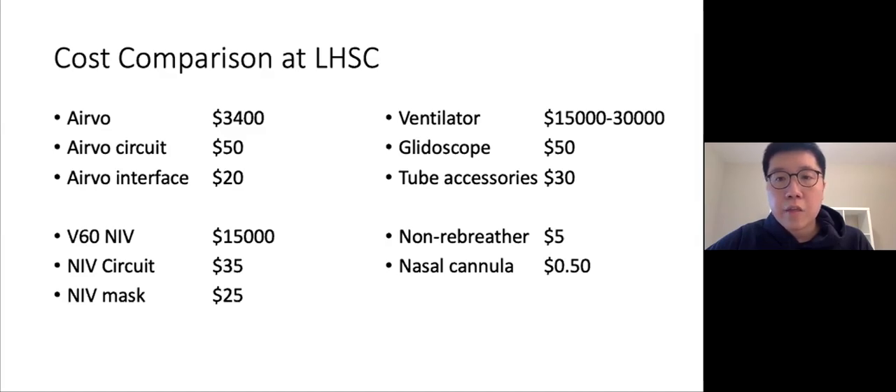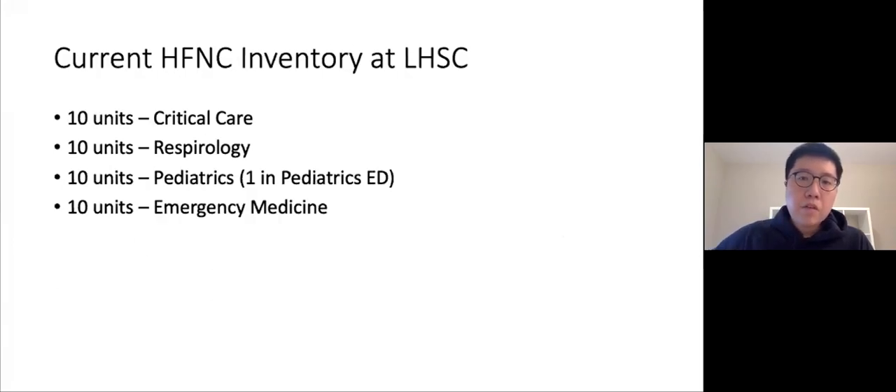One criticism about starting high flow in the emergency department is cost. The AirVo machine costs $3,400 versus $15,000 for the V60 non-invasive ventilator and upward of $30,000 for an intubation ventilator. The cost of the AirVo circuit and interface is also comparable to a non-invasive ventilation circuit and BiPAP mask. While more expensive than a non-rebreather mask or nasal cannula, high flow offers good value — especially if it can save a patient from intubation and ICU admission.